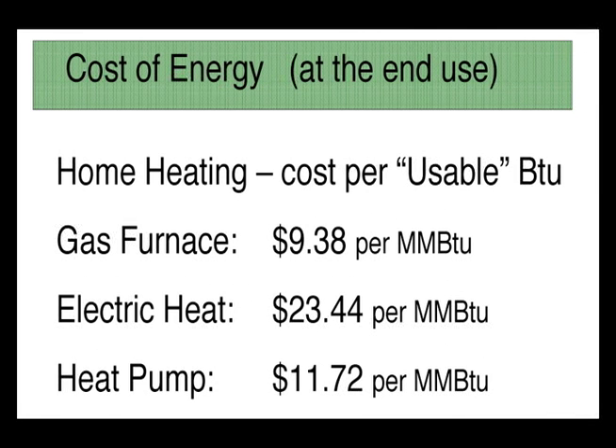So if you translate that to a cost per delivered BTU, the gas goes from 7.50 up to a number like 9. Electricity is still higher, because it's 100% conversion, something like $23 per million. And a heat pump, because of its a little bit higher efficiency, the cost to deliver heat that way is back in the ballpark of what natural gas is. So it's just to point out that as you think about how you're using energy, the efficiency of the process is also a factor as to how much it's costing you to get something done.